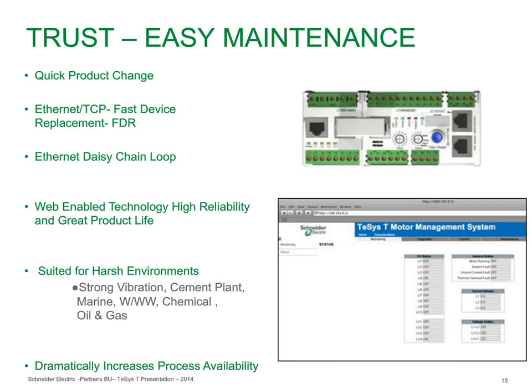We do have another function here for the Ethernet versions called FDR, or Fast Device Replacement. And this is actually a situation if you had a maintenance function where you needed to replace a device. The setup for that device, all the settings, will actually be assigned to an IP address. The settings will be stored in the unit itself, but it'll actually make a mirror of its settings on the PC or PLC that's controlling the unit. So when you put a new unit in, it'll actually detect the IP address and will actually download all the settings from your controller right back into the device, so no programming has to be done for maintenance. It'll all download automatically within seconds after it powers up.